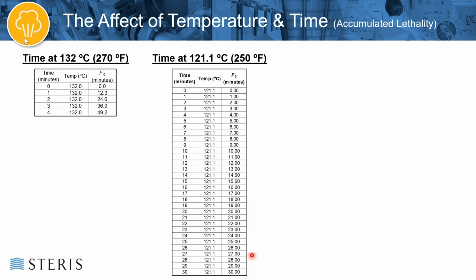So over here at 121 degrees C, it took 30 minutes to achieve 30 minutes of accumulated lethality. At 132 degrees C, we can see that somewhere between 2 and 3 minutes, we have acquired 30 minutes of F sub 0. So what that means is that at roughly 2.5 minutes of exposure at 132 degrees C, we have effectively delivered the same amount of energy, the same amount of lethality, the same amount of sterilization as a process at 121 degrees C for 30 minutes. So those two processes would be considered essentially equivalent as far as their lethality goes.